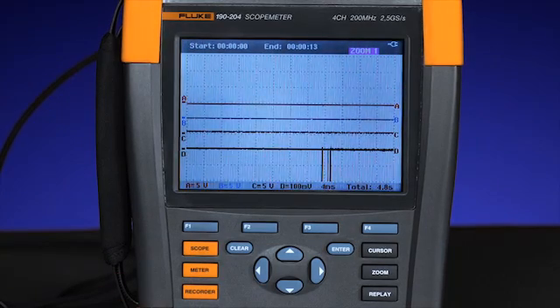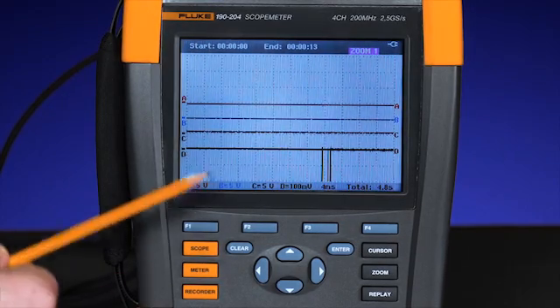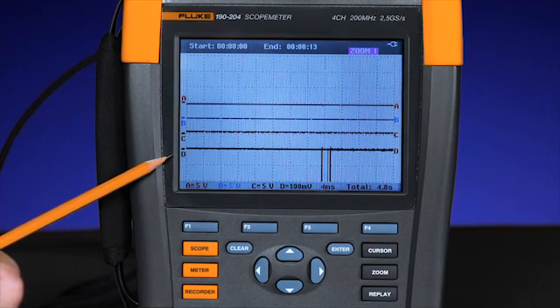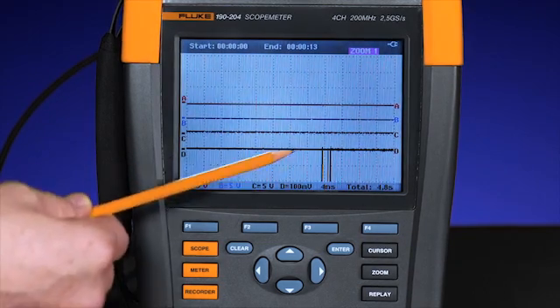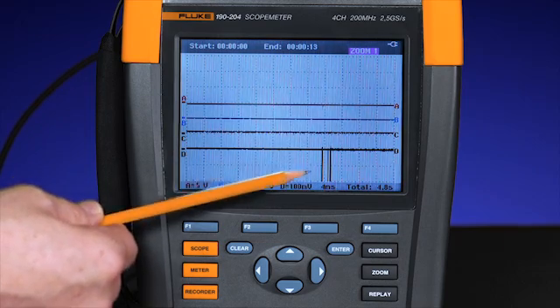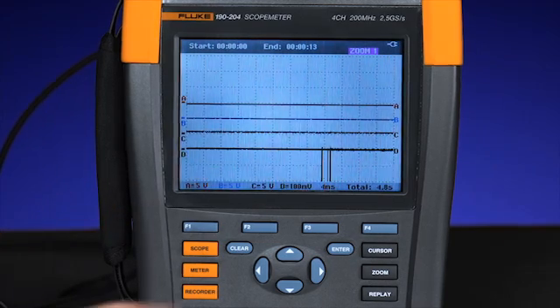What you'll notice in this instance is the input D, which has the current on the phase, saw a transient potentially causing the machine to go into overcurrent mode and shut down before it was able to completely start up.